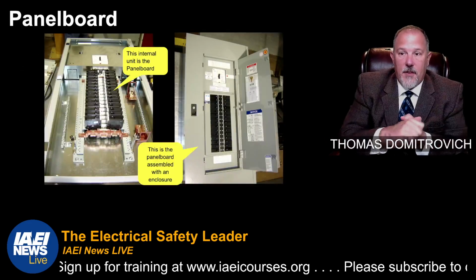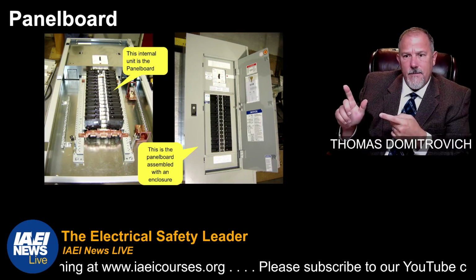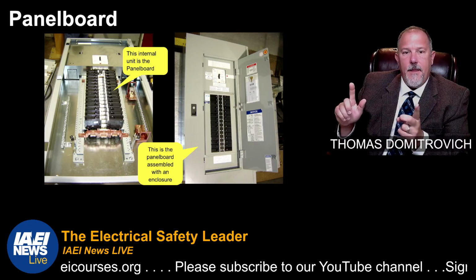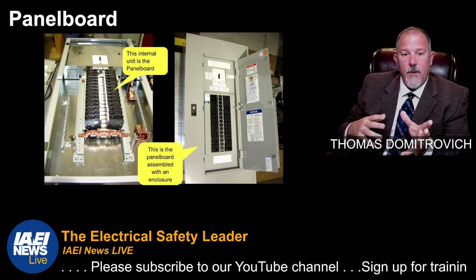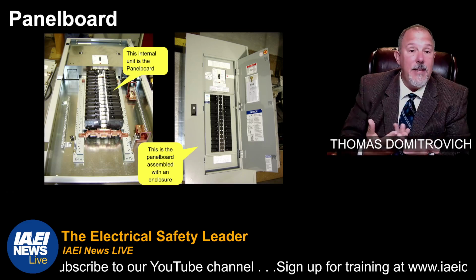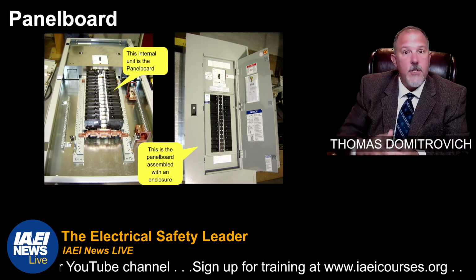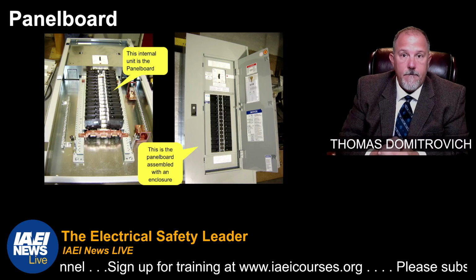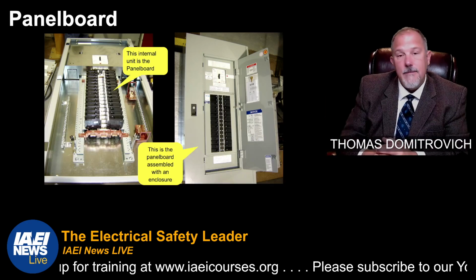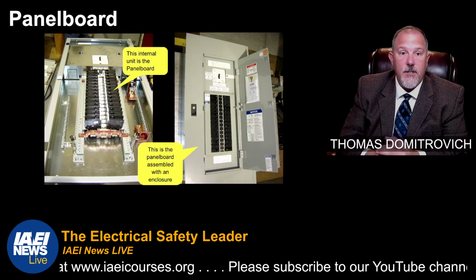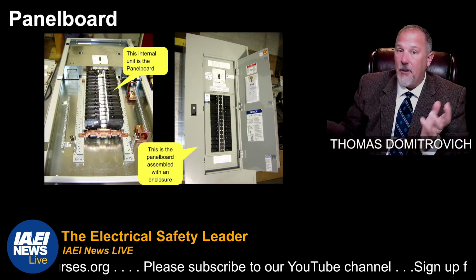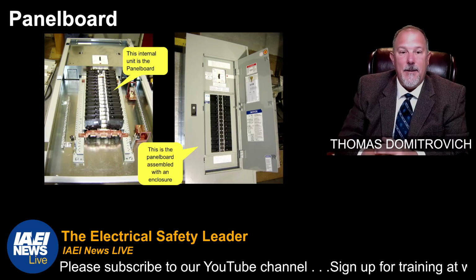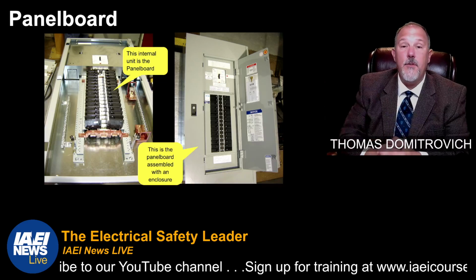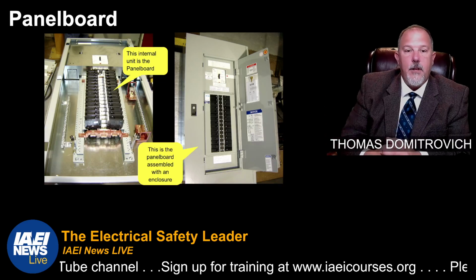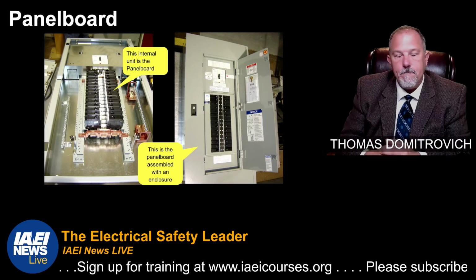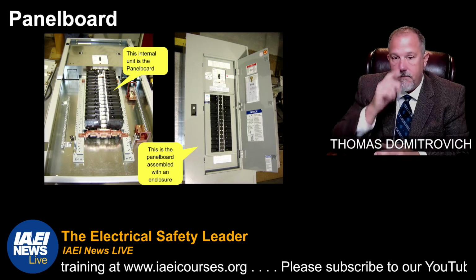So here's a picture. What you're thinking of, the one is on the right. I guess that's your right. And then there's the other, which is the internal. Now that internal piece can be taken out. In some cases, we'll ship the interiors and the boxes separately. And then you mount the interiors inside the boxes in the field. And that's convenient because you could just get the boxes put in, you can put your pipe in, you can get your wire in, and you don't have the interiors messing up the way. And the painters can come in and do what they voodoo that they do so well. And then you don't have to worry about them painting the bus, and then you bring in and put the interiors in. It can happen.